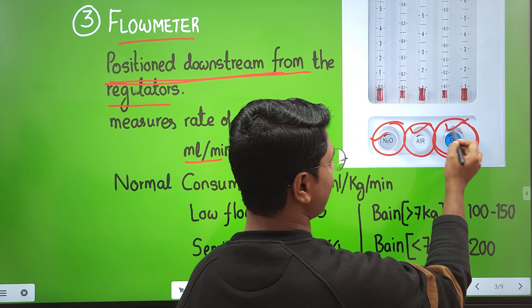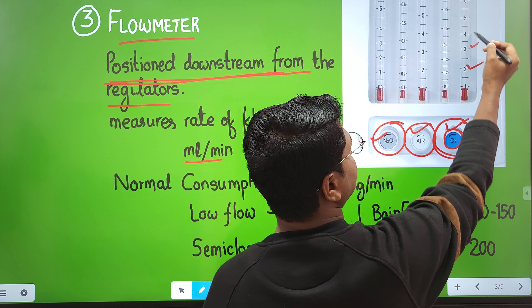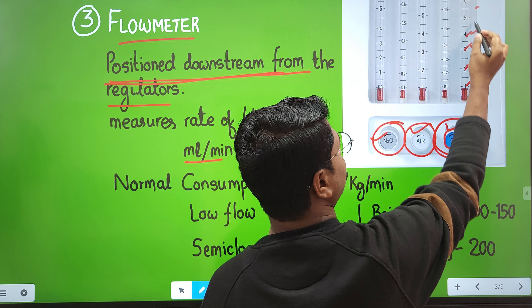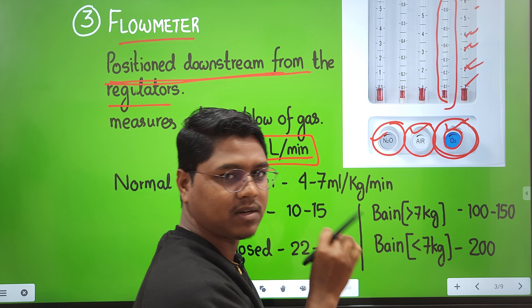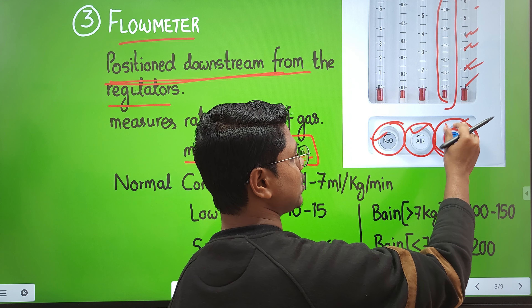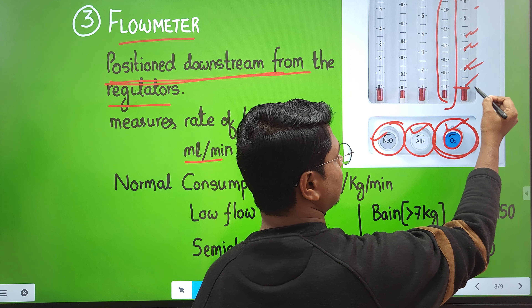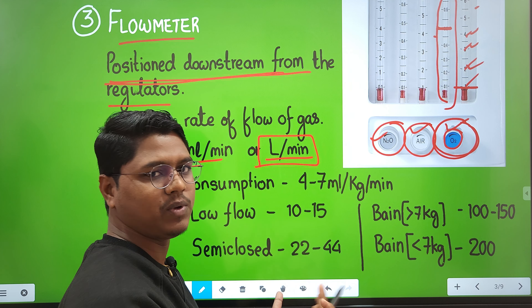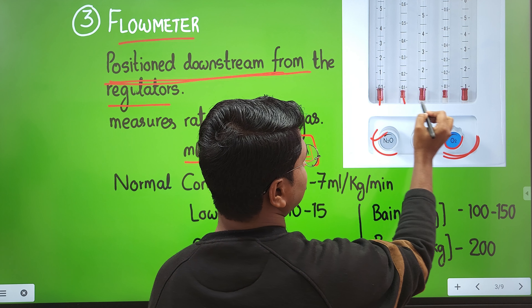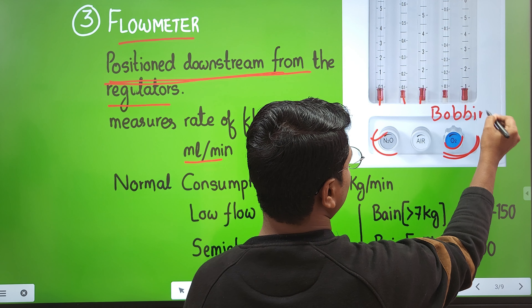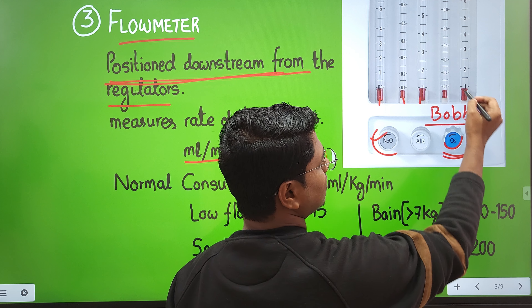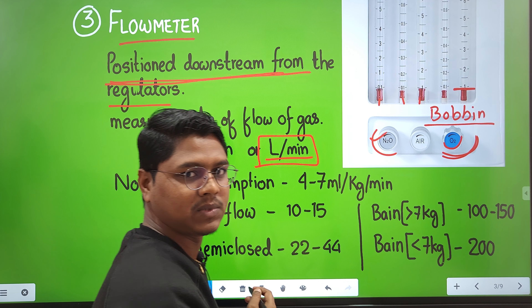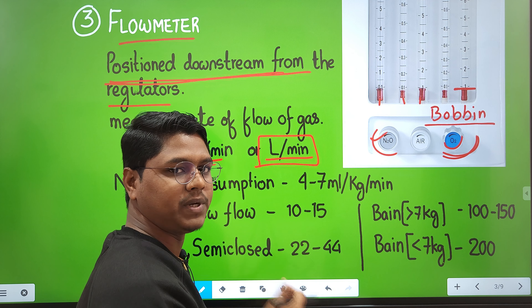Suppose you need the oxygen flow rate to be 1.5 L/min — you adjust the knob. The markings go 1, 2, 3, 4 liters per minute on one scale, and 0.1, 0.2, 0.3 on a finer scale. To set 1.5, you set one scale to 1 and the other to 0.5. The flow indicator is called a bobbin. If it is cylindrical, the upper mark is the indicator; if it is a circular bobbin, the central position indicates the flow rate.